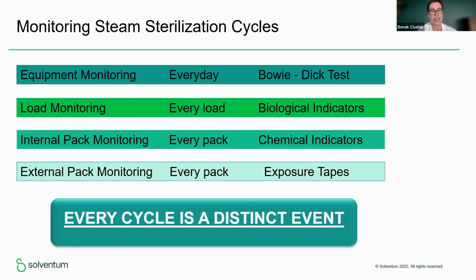When we focus on steam monitoring, we know that there are 4 levels to ensure sterilization assurance. First of all, we need to acknowledge that every cycle is a distinct event. So even if it is the same sterilizer, the cycles are quite different from each other. Therefore, we have to make sure that we are really performing these 4 steps to ensure sterilization quality and saturated steam. Equipment monitoring, we are familiar with, is the everyday Bowie-Dick test, and load monitoring is done by biological indicators, and the best practice is every load monitoring. In every pack, we place an internal indicator to see if sterilization conditions are reached inside each pack. And outside every pack, we have the external pack monitoring, and these are usually exposure tapes or labels.